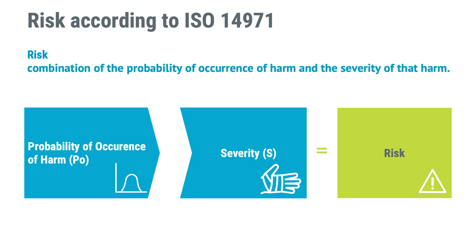This also means risk in the context of this course has nothing to do with corporate risk management or project risk. This is product safety risk. And just to be clear, risk in this context is not only about the users. Risks also include risks to users, patients, or third parties — or, to put it differently, just about anyone who comes close to the medical device.